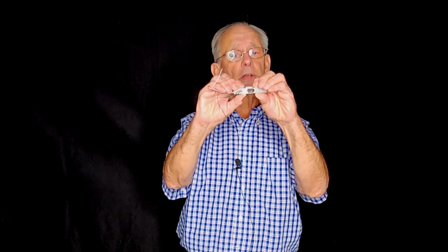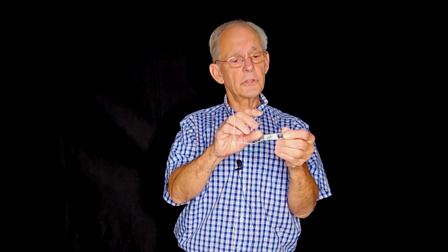Now, this is a really, really common technology nowadays because it's a very simple, very robust circuit with these strain gauges. This was used for us to test a screw that was putting on a high force, and we needed to measure somewhere around 4,000 pounds, and we used this to do it. But then this is also a strain gauge, and this strain gauge works exactly the same way. There are resistor elements in this bridge, and when this bridge deflects, it puts out a signal. The signal that this puts out and the signal that the big one put out are exactly the same. So the instrument that reads the big one and the small one is the same device.